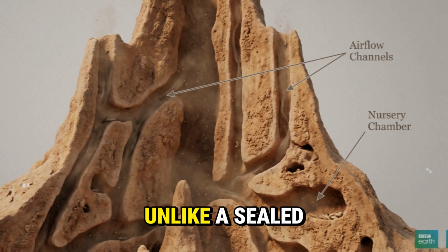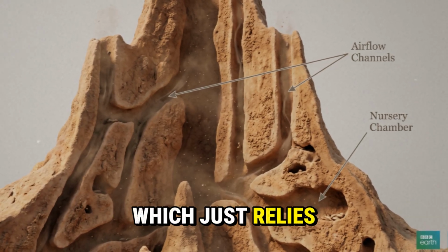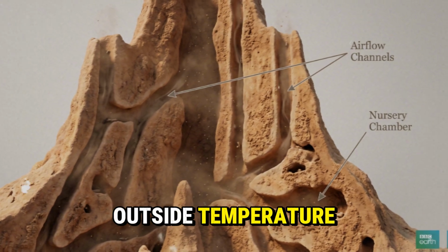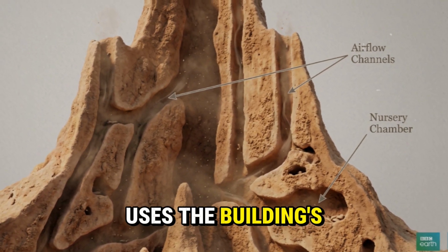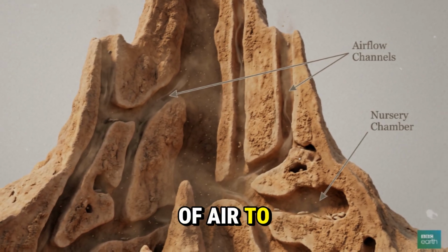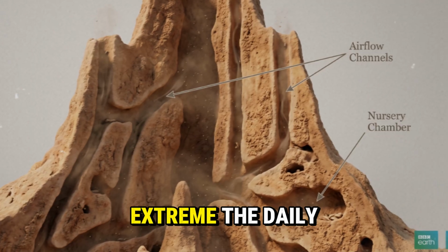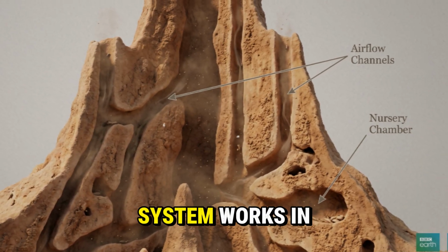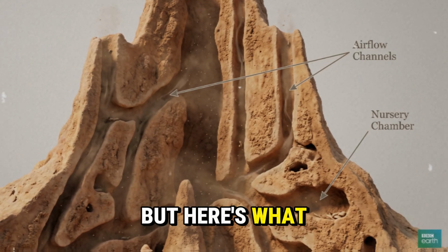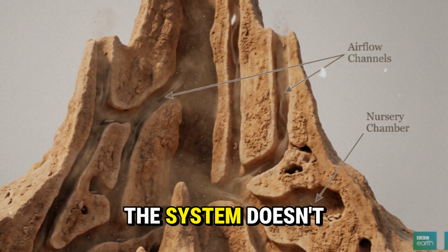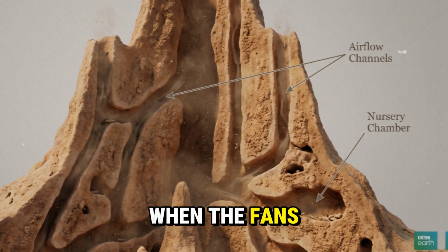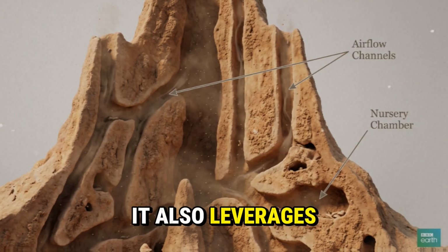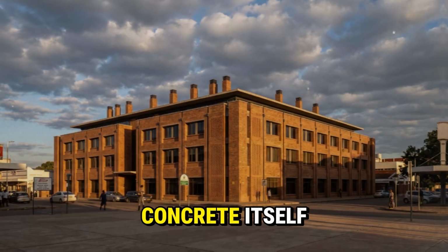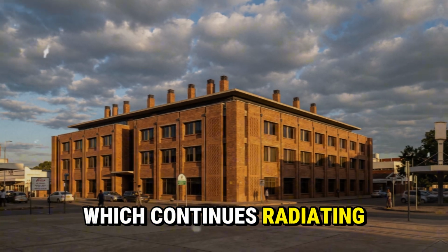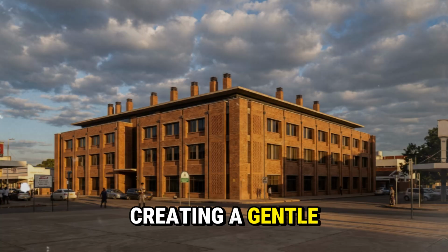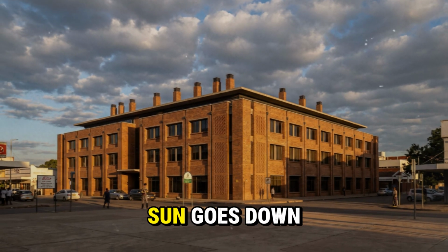The key point here is that unlike a sealed office tower which just relies on brute force refrigeration to fight the outside temperature, the Eastgate Centre uses the building's own mass and the movement of air to do most of the work. And the more extreme the daily temperature swing, the harder the system works in its own favor. But here's what most people don't realize. The system doesn't stop regulating temperature when the fans are off. You see, it also leverages the enormous thermal inertia of the concrete itself, which continues radiating stored coolness for hours, creating a gentle temperature buffer that persists long after the sun goes down.